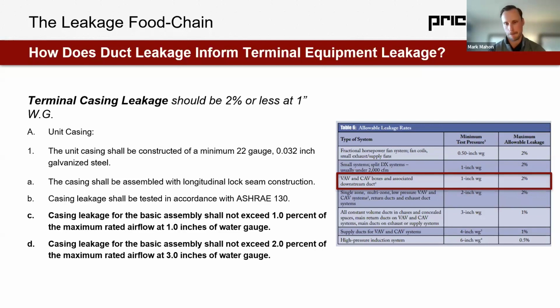If ASHRAE says, yeah. Yeah, just real quick, I think you said it, but I'm just double checking. If I have a 10-inch box, 1000 CFM max, 300 CFM min, it's 2% of the max, so 20 CFM, okay. Correct, maximum rated airflow. A 10-inch box is a great example. At 2,000 feet per minute, we're often seeing it selected around 800 CFM at the upper limit for max cooling applications. That 800 CFM at 1 inch of pressure should be leaking 8 CFM, so 1% of 800, and 16 CFM if we're looking at 3 inches. And that's just the stock standard out of the box terminal, at that maximum cooling rated airflow. Got it. Thank you. You bet.